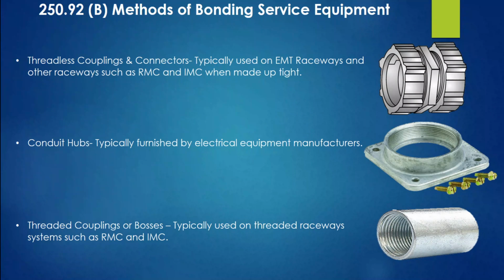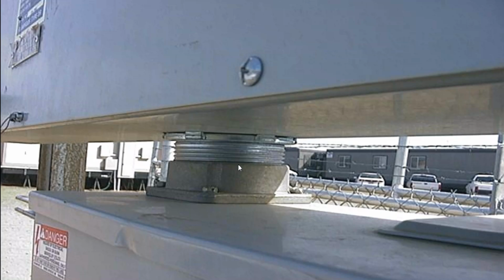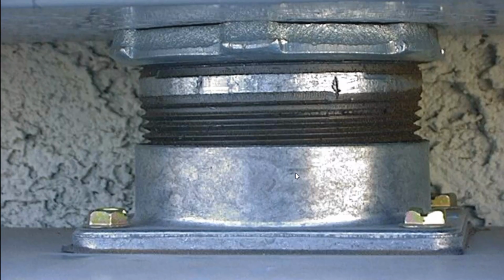Now, those other ones, I just wanted to give you some illustrations. Threadless couplings and connectors, kind of similar to this. Again, used in RMC, IMC, and again in EMT as well. Hubs, we see all these hubs on a lot of the graphics I use coming in. It's a threaded entry. These screws screw down into the equipment, making a good solid connection through the threaded entry. And then, of course, here's the threaded coupling we were talking about, let's say for a rigid conduit raceway or IMC. All of that does give you adequate means to maintain the connection between all those components that have service entrance conductors within them. Here's an example of the hub, and here is an example of a standard lock nut being used for mechanical purposes connected for this equipment. I have no idea what's done in here, but this enclosure is connected here, so this nipple is connected to here, which means that this one is bonded per this application here. Here's just a close-up of that application.